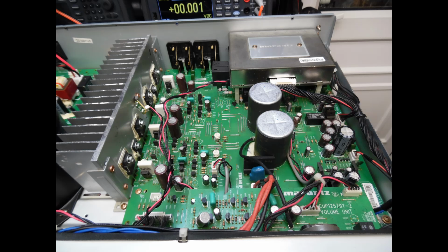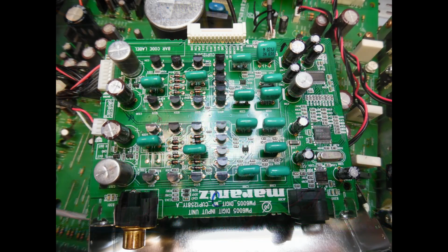Now, once the module is removed, what you can see is it's completely encased in metal, and what I show here is the circuit board removed. So very carefully, and again to avoid damage, you can use, for example, a plastic tool to prise off the top casing, and then when you look at the module, you'll see there are a number of grounding tabs where the circuit board is soldered directly to the metal case, effectively providing a Faraday shield or EMF type shield to reduce the amount of electrical noise.